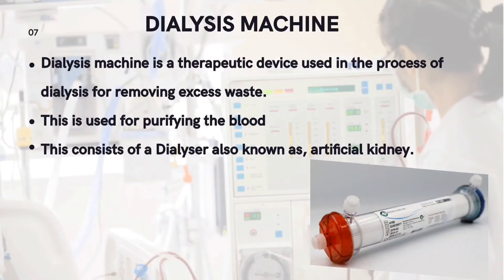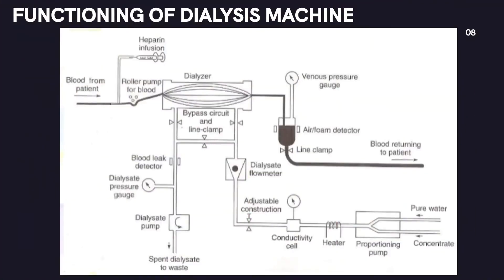What is a dialysis machine? A dialysis machine is a therapeutic device used in the process of dialysis for removing excess waste and purifying the blood. It consists of a dialyzer, also known as an artificial kidney — a semi-permeable membrane containing dialysate, a mixture of water and electrolytes. Blood is removed from the patient through a catheter, purified in the dialyzer, and pumped back. Excess urea and salt are removed, and an anti-coagulant heparin injection is present to prevent blood clotting.